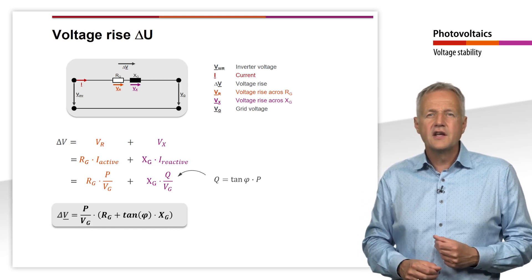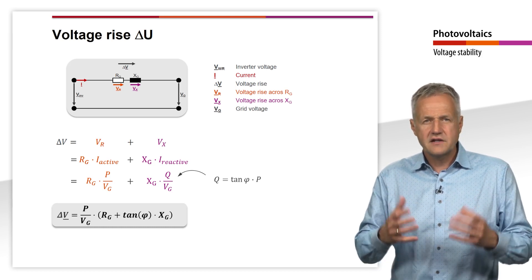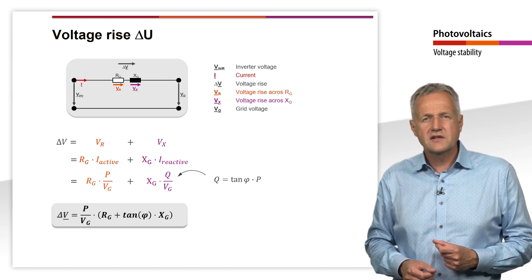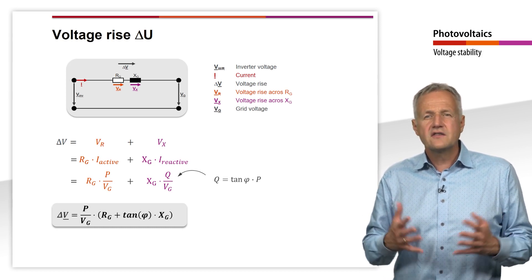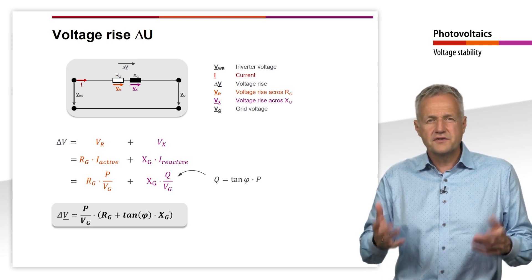Not surprisingly, the voltage rise depends significantly on the active power P fed into the grid. We also see that in addition to the magnitude of R and X, the phase shift set on the inverter also has an effect on the voltage rise.